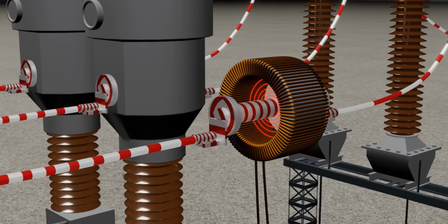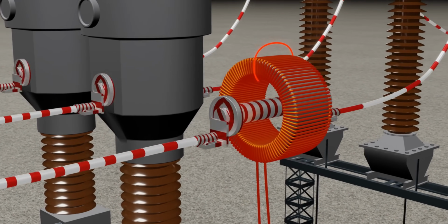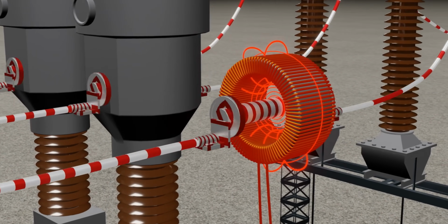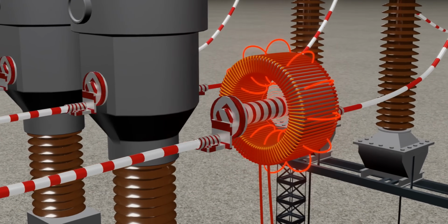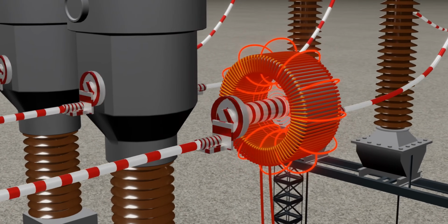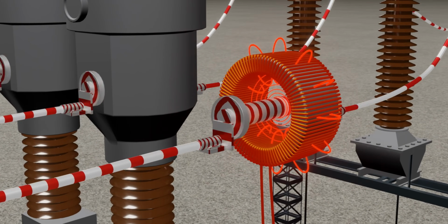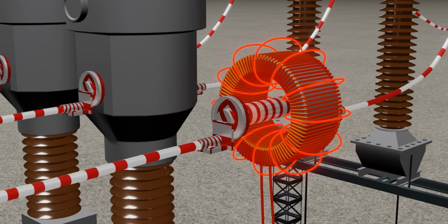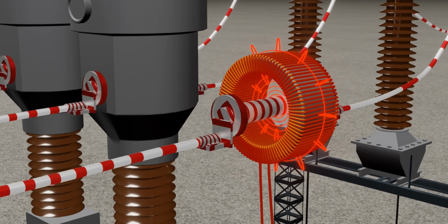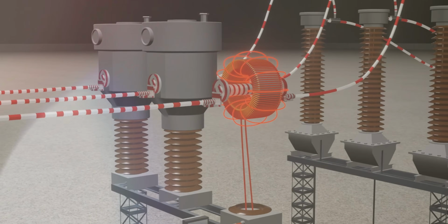We'll explain the working of a current transformer in a future video. But in short, a CT steps down the high current to a safe standard level, usually 1 or 5 amperes, depending on the system. This lets relays and meters measure large currents without direct contact with high voltage circuits.